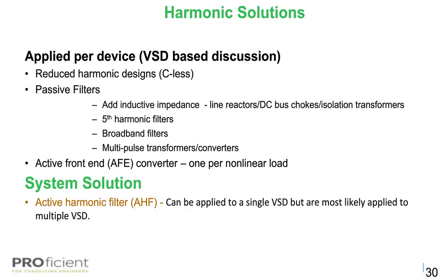So, in short, as we continue our discussion, for the next couple of solutions I'll really focus on a 6-pulse VFD drive, and then I will do several comparisons to both passive and active filter solutions, and basically the current designs out in the marketplace and how they compare based off your applicable system. So first, we'll discuss the reduced harmonic designs, which is C-less. Then we'll get into the passive filters: added inductive impedance, fifth harmonic filters, broadband filters, multi-pulse transformers and inverters. Then we'll discuss quite intensively the active front-end converters, and then we'll get into some active harmonic filters. They can be applied to both single nonlinear and multiple nonlinear loads.